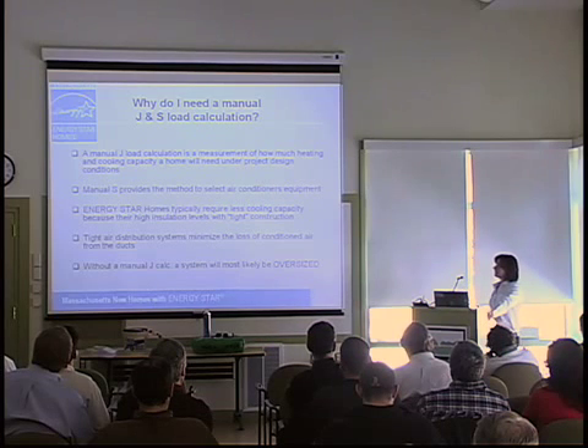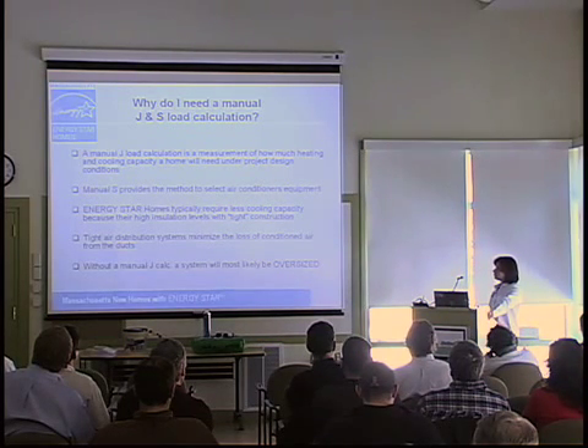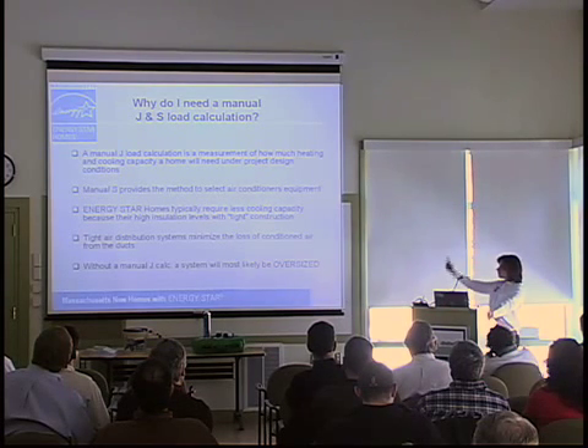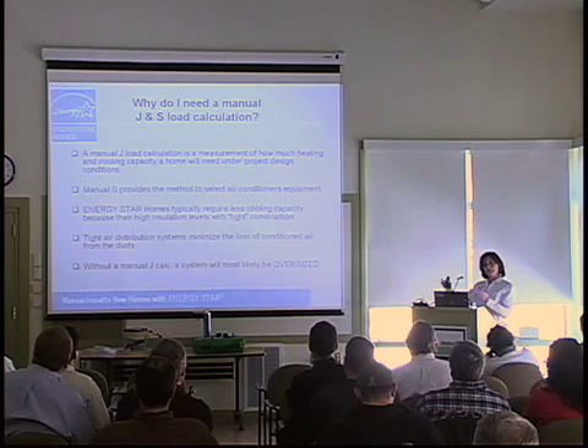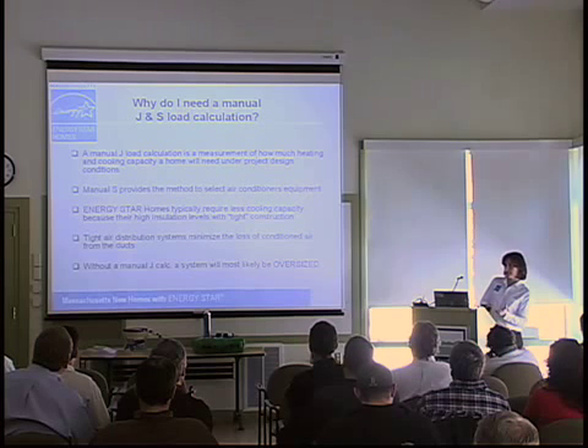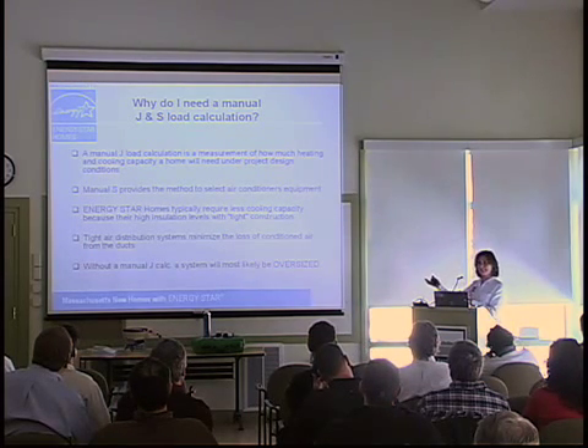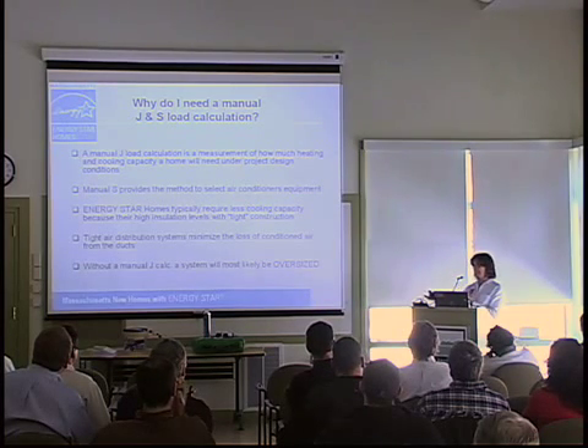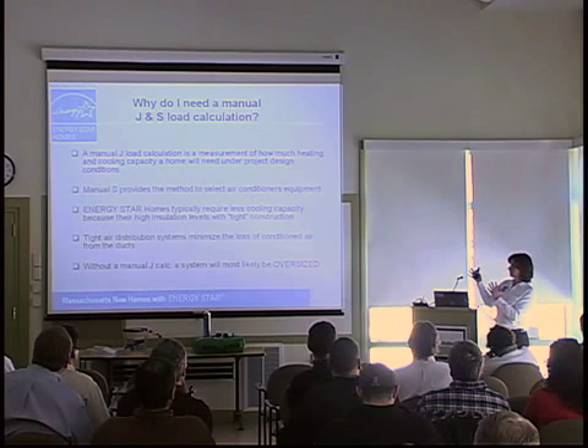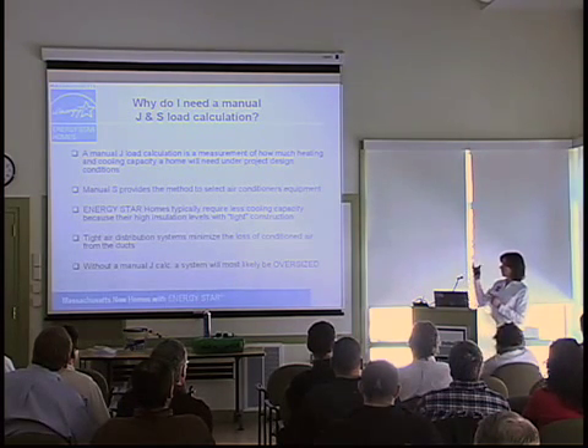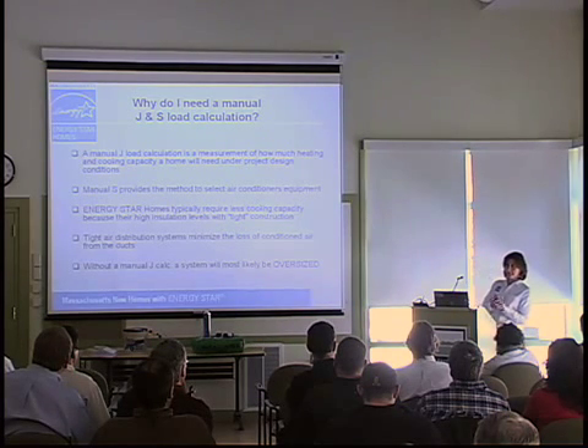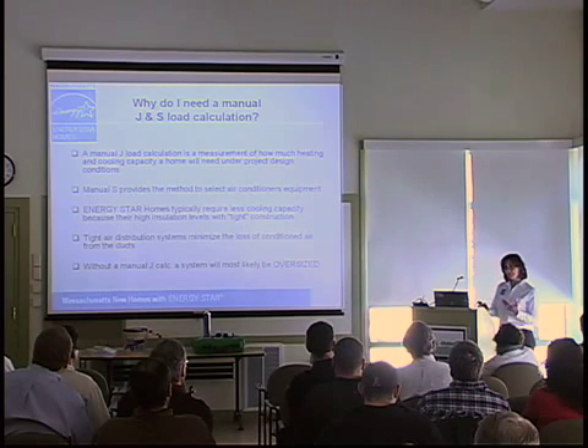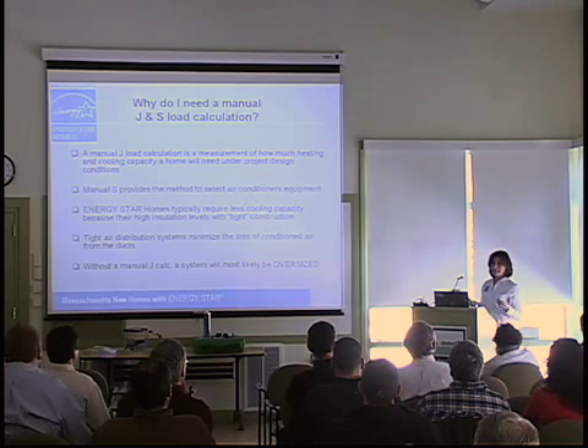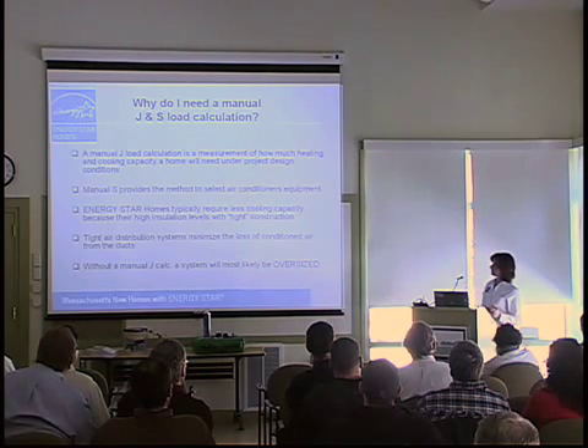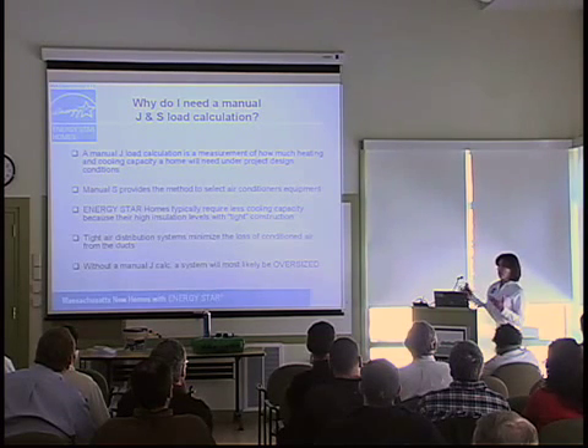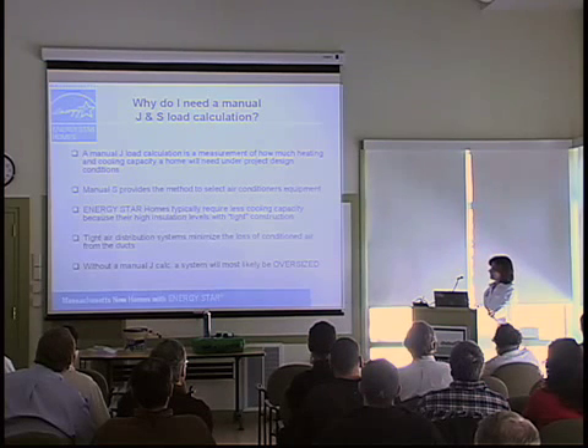But a Manual J load calculation is basically a measurement of how much heating and cooling capacity a home will need under project design conditions. So we talked about those design conditions. That would be your outdoor temperature for that particular area and your indoor temperature. So basically, on the hottest, over time and recorded weather data, the hottest possible day that they've recorded, most likely be 87 degrees. So we need to size the cooling equipment to maintain 75. Doesn't necessarily mean that if somebody punches the thermostat and wants it to be 72, that it won't operate, but it just actually is just the way the manufacturer designs the equipment and the way it stages itself to handle the loads and the changing loads within that house.